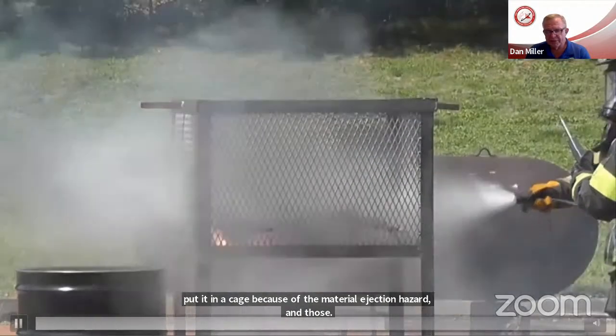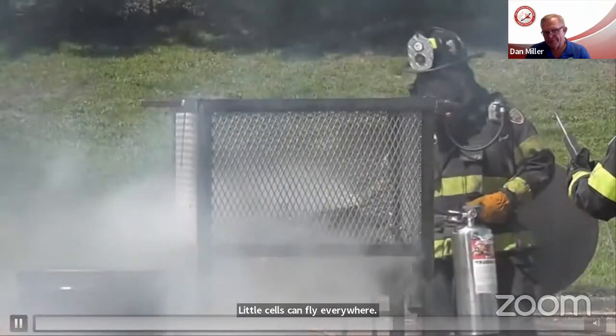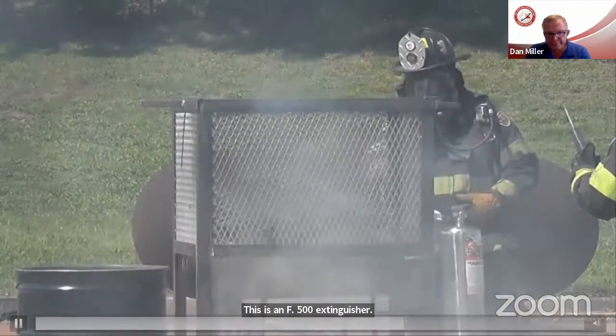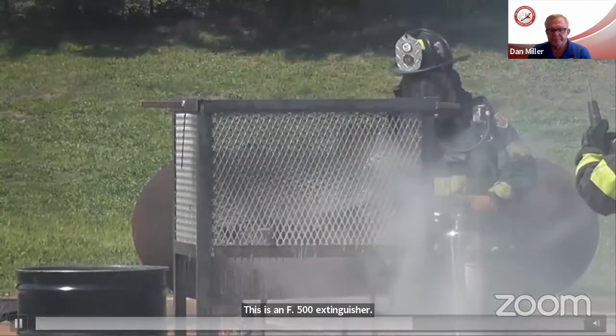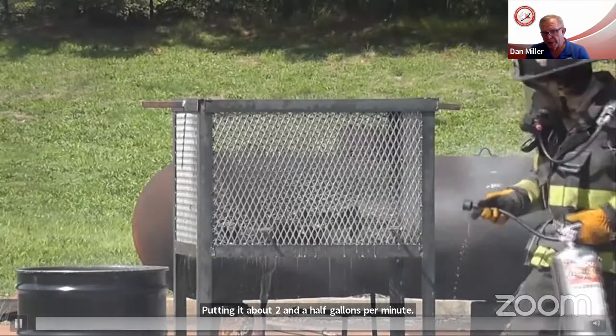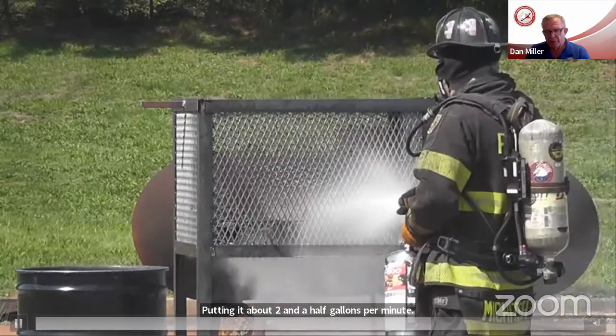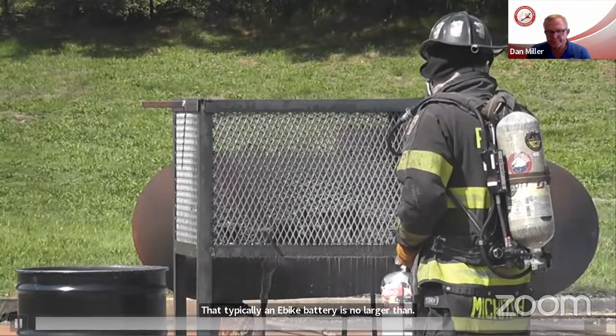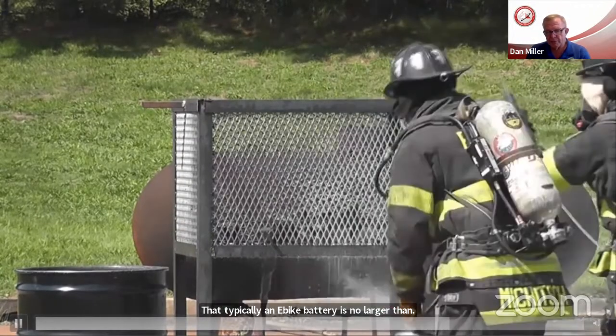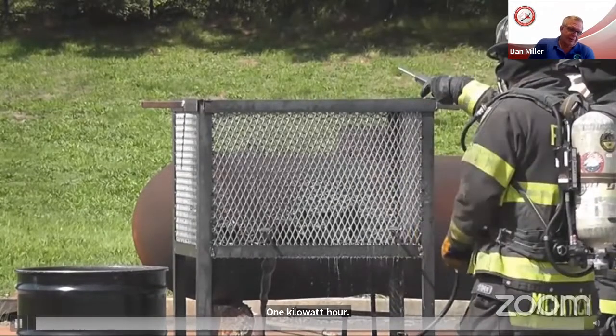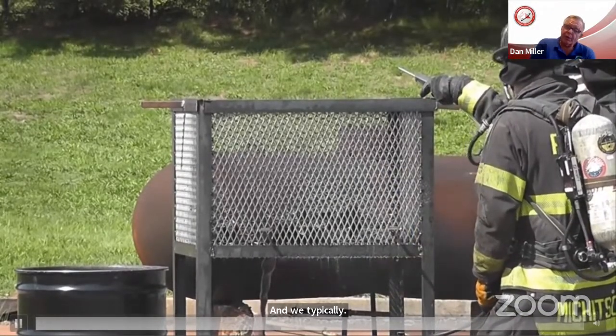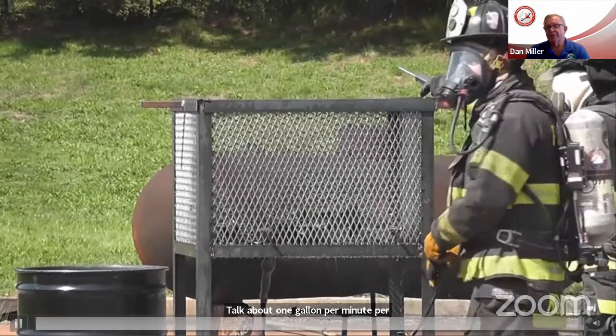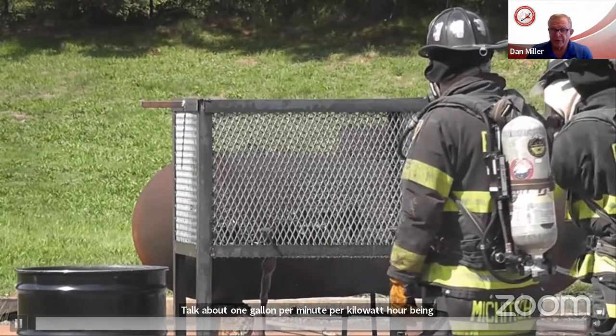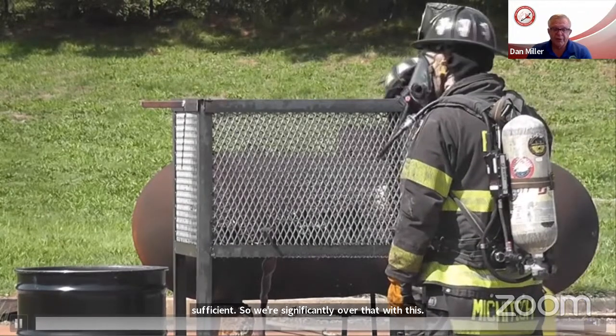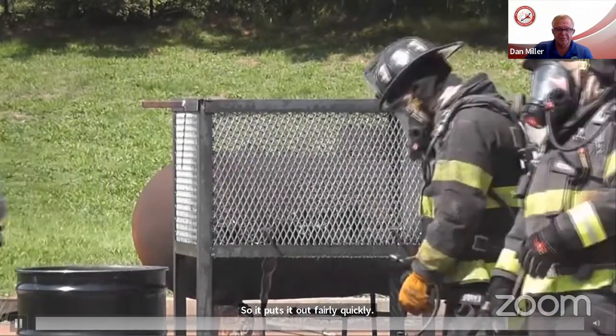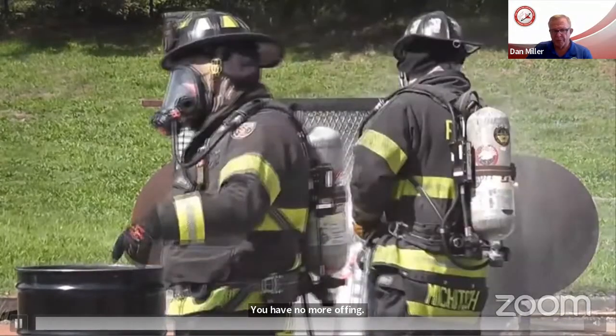This is an F500 extinguisher, putting out about 2.5 gallons per minute. An e-bike battery is typically no larger than 1 kilowatt hour, and we typically talk about 1 gallon per minute per kilowatt hour being sufficient, so we're significantly over that with this. It puts it out fairly quickly—no more off-gassing, no reignition problem. It handles those small incidents pretty quickly.